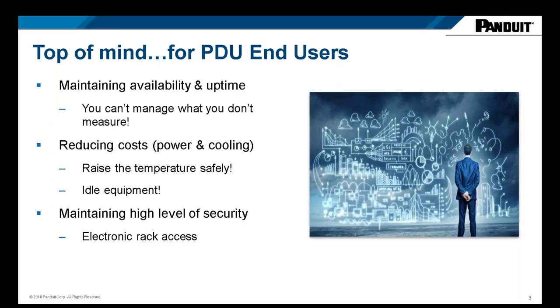In fact, there's a study that found for every 1 degree you're able to raise the ambient temperature of the entire room safely, you're saving 4% on cooling costs. That resonates with people, and that really drives the requirement for rack power distribution units - and really every piece of equipment in that room - to be able to withstand higher operating temperatures.